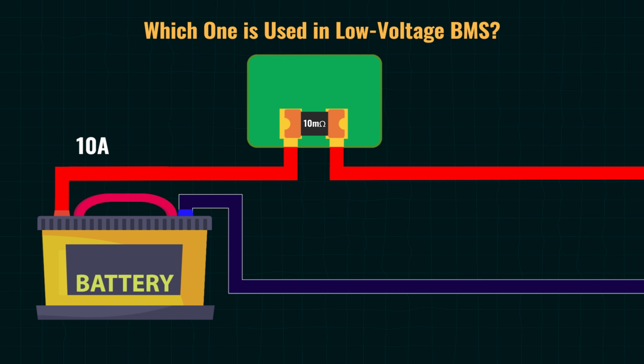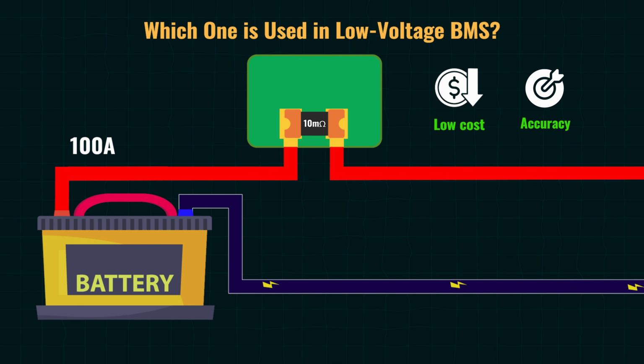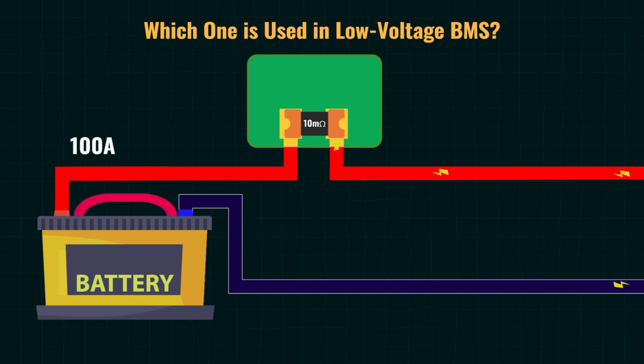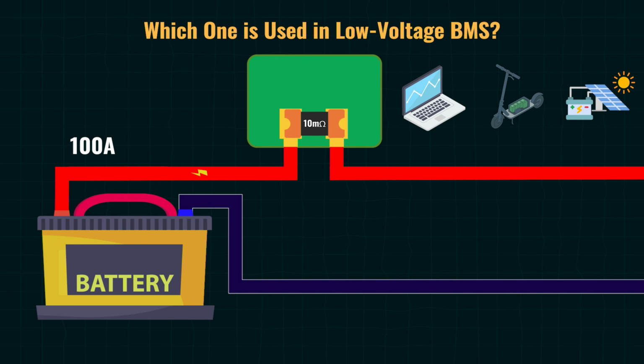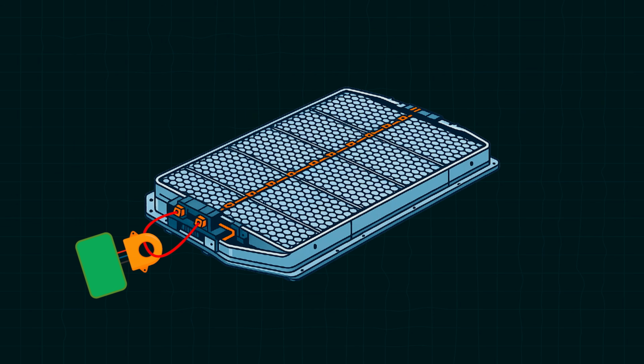You guessed it right. A shunt-based sensing is more reliable for low current, especially less than 100 amperes, and low voltage BMS less than 100 volts. Why? Because in systems like 12 volts, 24 volts, or 48 volts battery packs, isolation is not needed, but cost and accuracy matter a lot more. That's why we find shunt resistors in everything from laptops and electric scooters to home inverters. Hall effect sensors are great when we want to handle very high current, like 1000 amperes or more.